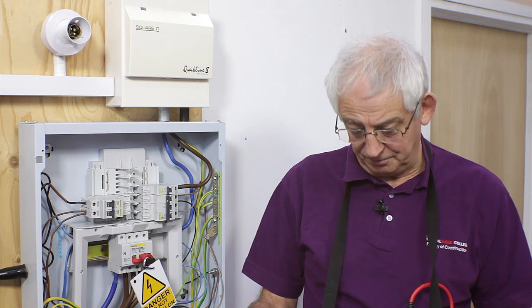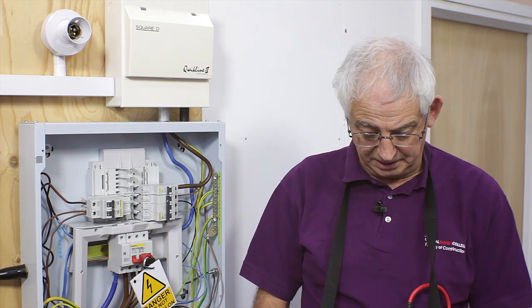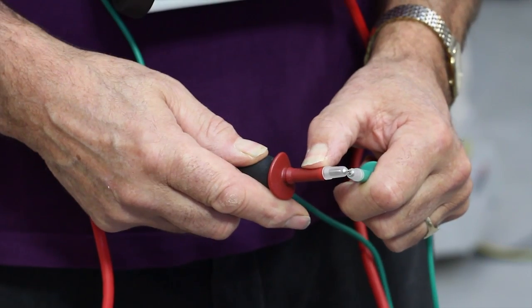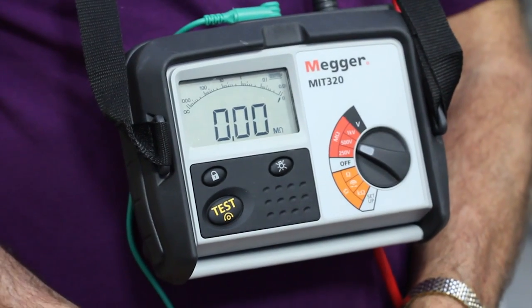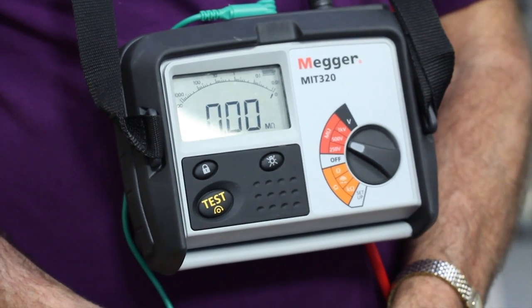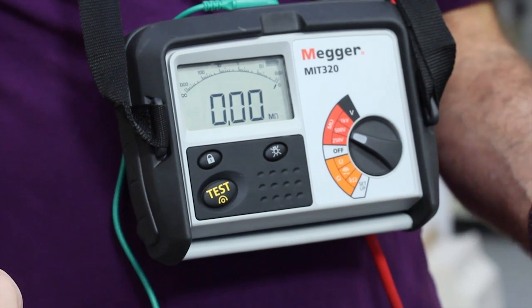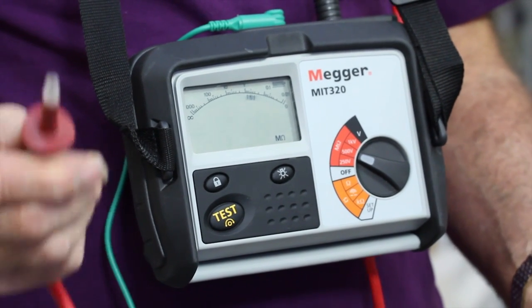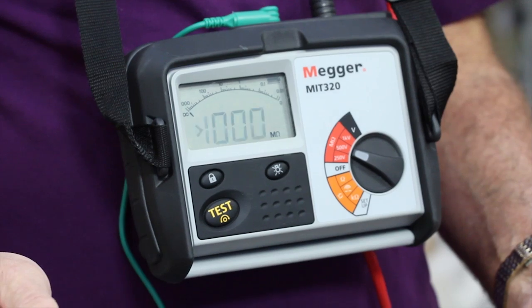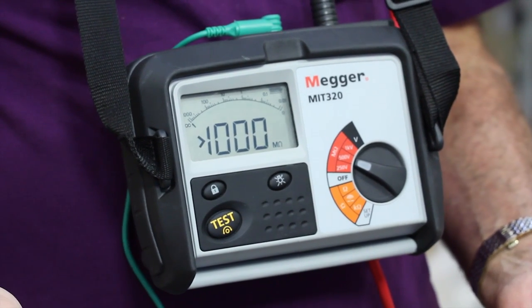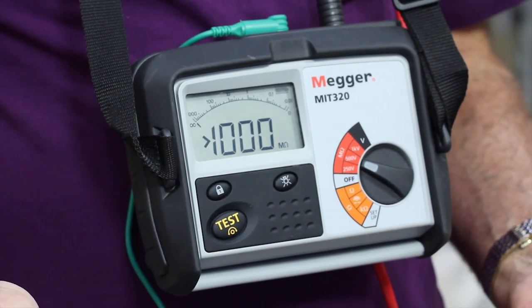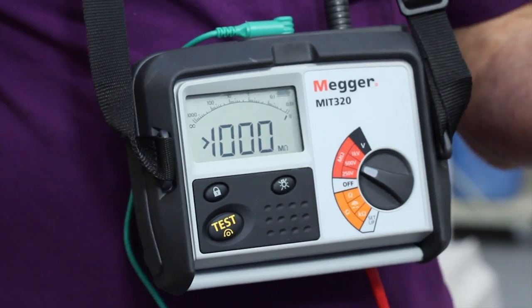So to do that, first of all, I need to do a test with the leads together, push the button, and you can see I've got a very low reading. In fact, I'm getting 0. Carry out the same test with the leads apart, push the button again, and now the reading should be over range. Okay, with that done, I know full well that the instrument is working properly.